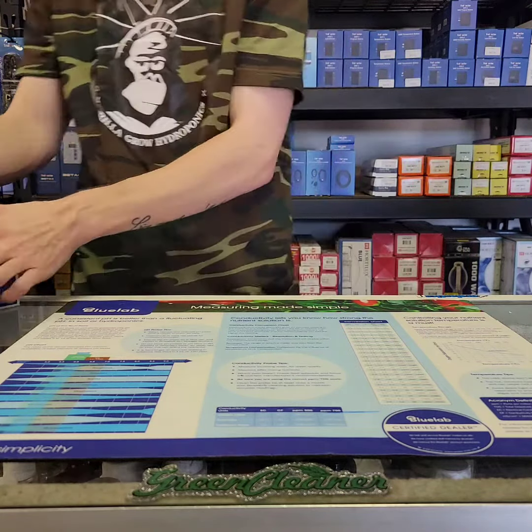Now we're just going to go ahead and give it a quick calibration. This pen is going to use the 7. I'm going to go ahead and get both just in case it's set to the 4 setting. And after that we're ready to dunk the pen. So once you get into the solution and the probe is submerged, go ahead and hold the calibration button. It's going to go right into calibrating, and this one is attempting to read the 7. So we're going to let it do its job, and once it's done, the numbers should stop flashing.